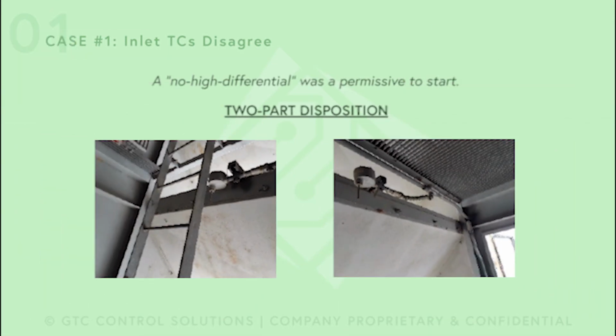This is a picture of the thermocouples that were giving trouble. The one on the left is the one on the west side. The one on the right is the one on the east side of the unit. As you can see, the boxes are pretty similar in size, so we can use them to scale the distance, and it seems like the one on the west is much closer to the wall than the one in the picture on the right. That also explains why they were seeing this high differential.